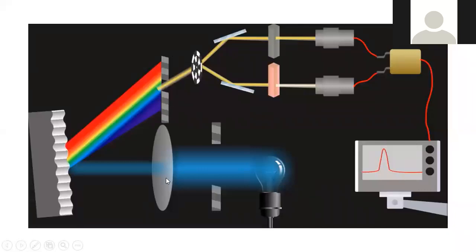Combining these four things gives you the monochromator. Then you have the chopper, then the mirror, then the reference and sample container — we call it the cuvette — which holds the reference and sample solution, also called the sample holder. After that, we have two detectors, then the amplifier, and then the recording device. Now we will explain the instrumentation of all these things.